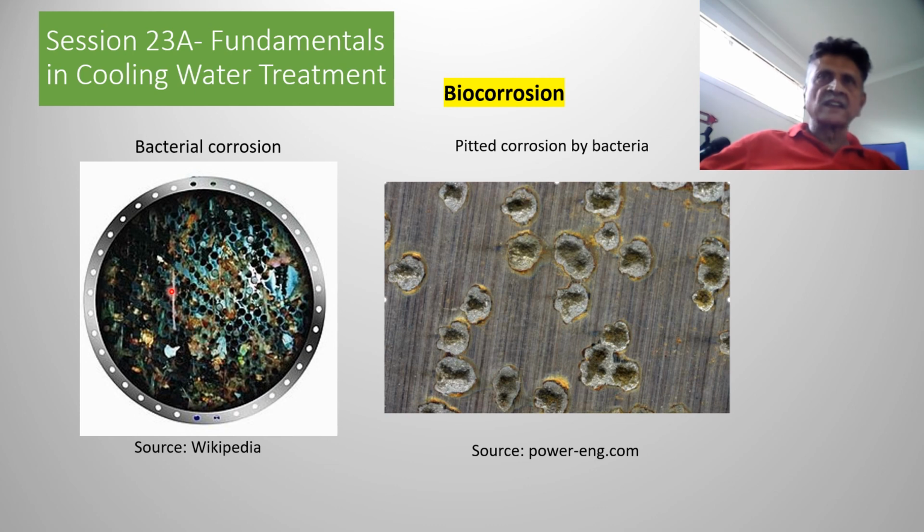Holes also occur in the copper tubing, and it will start mixing with the air conditioning liquid which flows within the copper tubing. Here is a more blown-out picture of the side of your pipes. You find that wherever the bacteria have accumulated, the acids generated will cause holes, and the holes will resemble the pits of pitted corrosion.